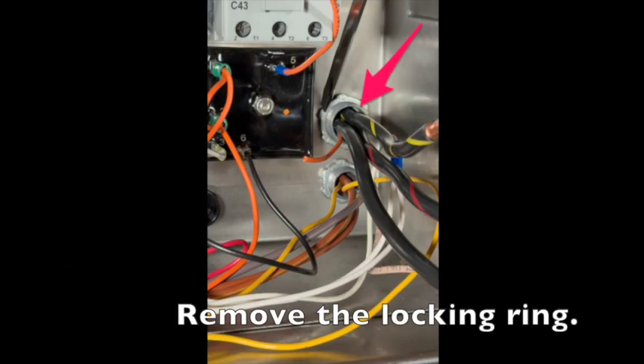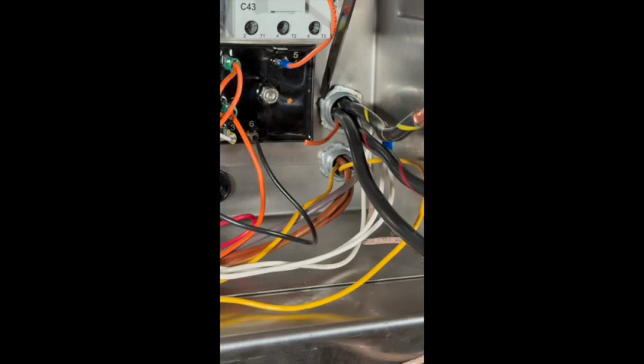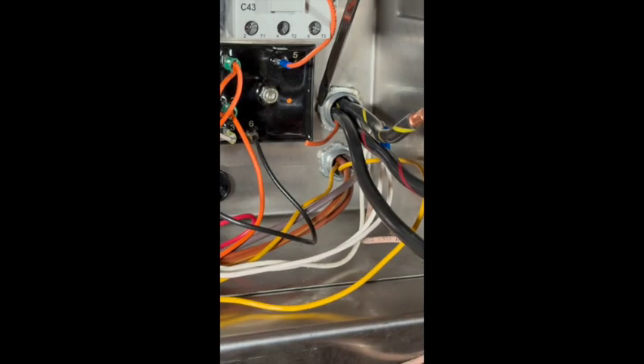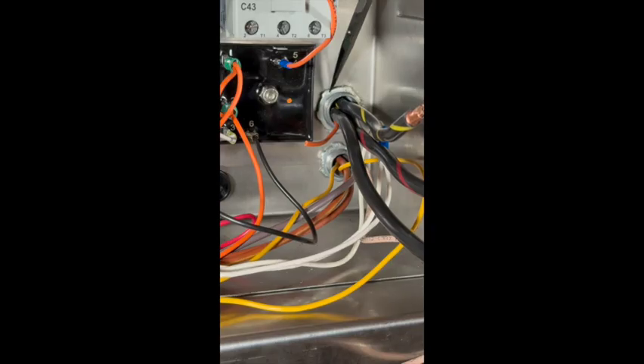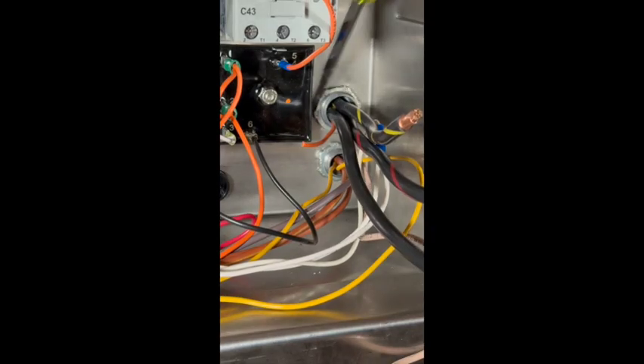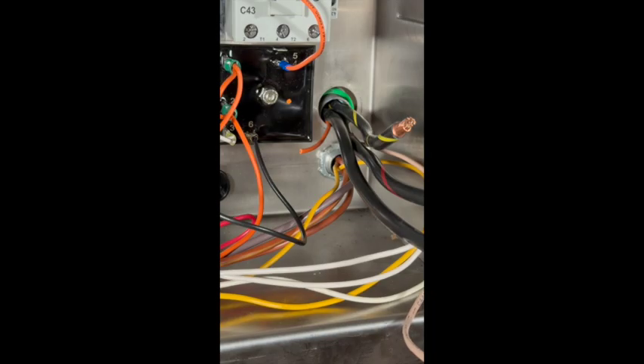So I ended up taking off the conduit completely off the machine, undoing the electrical wires that were on the wash heater contactor, and just completely taking out the conduit from the machine itself.